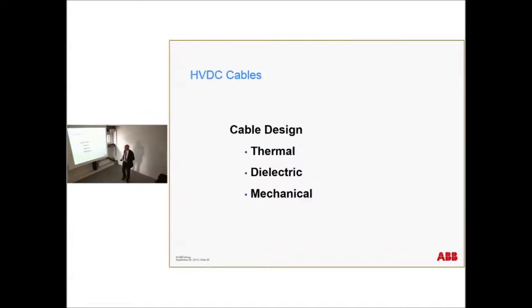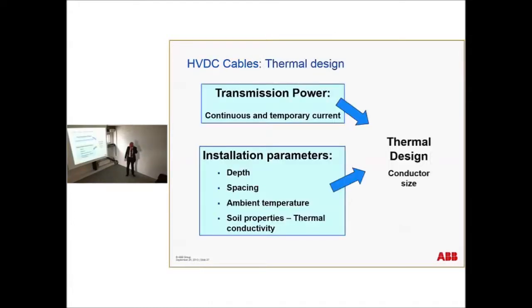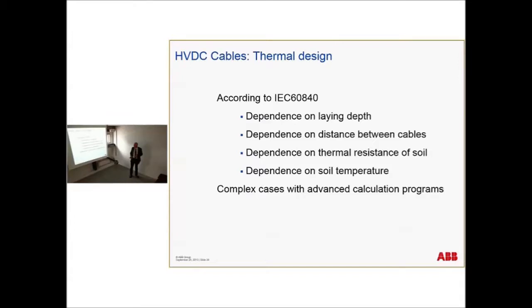If we talk about the design of the cable, it must be designed thermally, electrically and mechanically. We start with the thermal design. It's rather obvious that the higher the current, the higher the ambient temperature, the less space, and whether you have good thermal conductivity in the soil or not, it will give the conductor size, in order not to exceed the maximum allowed temperature of the conductor during service. This is according to IEC standards. It's pure mathematics, I would say.